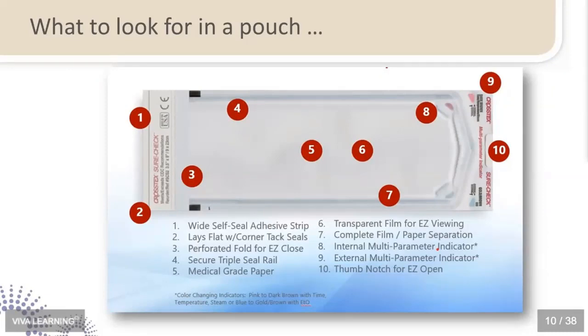We also know that many of our pouches that are available today have built-in chemical indicators, because this is one of the guidelines from CDC. We must have a chemical indicator inside each pouch or package. And if that chemical indicator is not visible on the internal, in this case it is, then an external indicator is also required. Now, some of you may see pouches like the one here, where there's a chemical indicator on this side and there's a chemical indicator on that side, and they're 2 different colors. Reason being, it's 2 different sterilization methods that have been validated for this particular pouch.